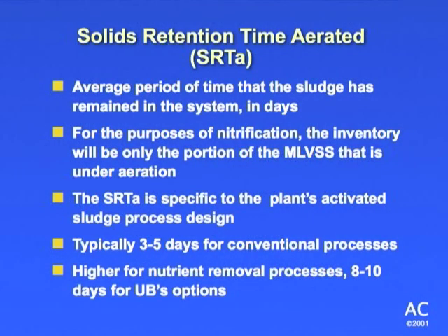The next thing I was going to get to is solids retention time. So what is the solids retention time? It's basically the average period of time that the sludge has remained in the system in days. Oftentimes people say it's the sludge age. Another way of saying it, similar, is the mean cell residence time. But we tend to work with solids retention time.